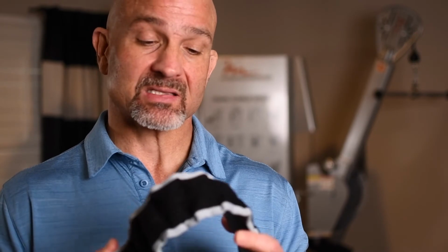So when you're evaluating your cuffs, I'm not saying a particular type of device that you should use or anything like that, but be critical when you look at these things. It's not the width of the cuff. Pump it up and see what is the occlusion area. And remember that slide where that pressure drops off pretty quickly just outside of that peak area. This is a really critical point.